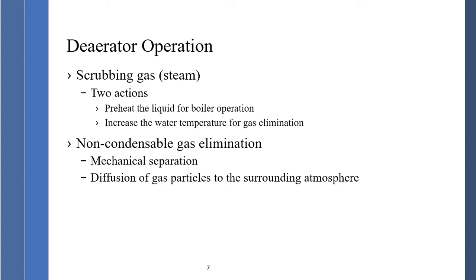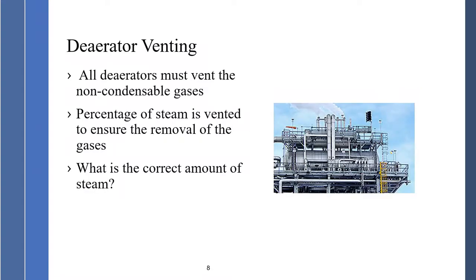Deaerator operation is scrubbing gas. Steam has two actions: preheat the liquid for the boiler operation, and increase the water temperature for gas elimination. Non-condensable gas elimination can be mechanical separation and diffusion of gas particles to the surrounding atmosphere. All deaerators must vent non-condensable gases. A percentage of steam for the operation is vented to ensure the removal of gases — in this picture, you can see non-condensable gases or steam being vented to ensure we are getting rid of the gases out of the deaerator operation.